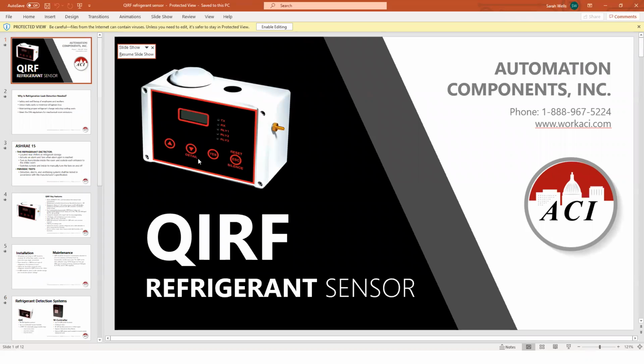All right. Can you see the new screen? Yep. Okay, so basically our Freon detection system, QIRF, I'll just generalize right off the top. What I really like about this is it's simple. One sensor covers 7,500 square feet. If you have 2 chillers that are the same Freon, you don't need to have 2 sensors. You can put it in the middle, mounted about 12 to 18 inches off the floor. Very easy, no sampling tubes.